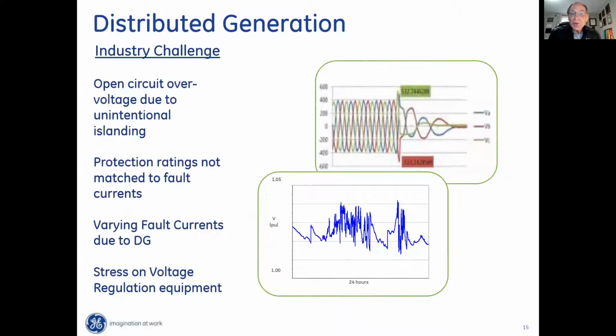One challenge is open circuit overvoltage due to unintentional islanding. Second is protection ratings that no longer match fault currents. When we do a protection study, we first do a short circuit study, since we need to know the magnitude of fault currents so that protective relays have the correct settings.